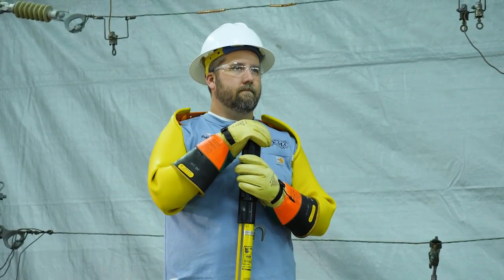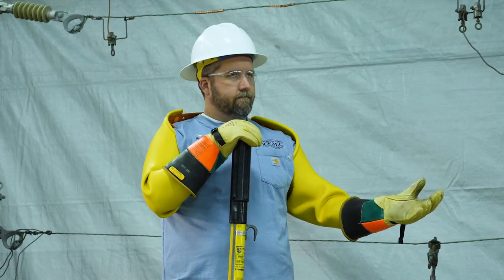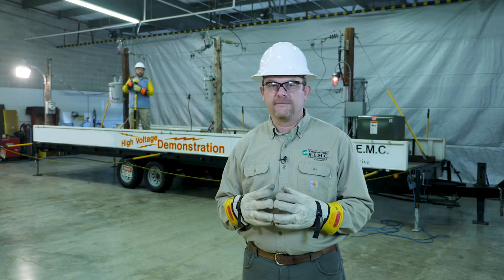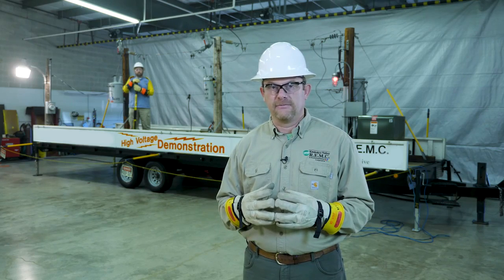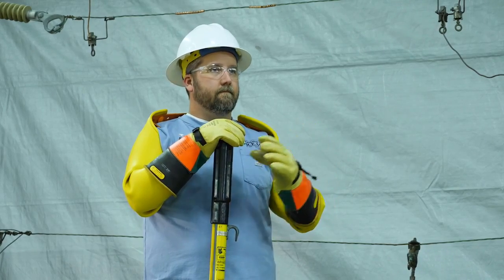The gloves and sleeves are tested against failure at 20,000 volts, but have a maximum working voltage of 17,000 volts. The gloves are covered with leather protectors, which look like normal gloves, but they're there to protect the rubber from snags or tears.